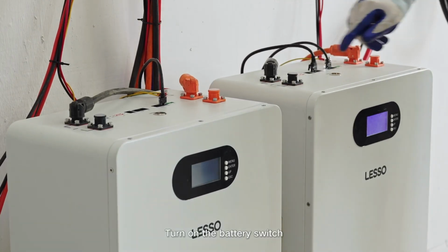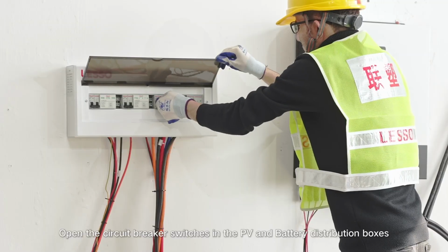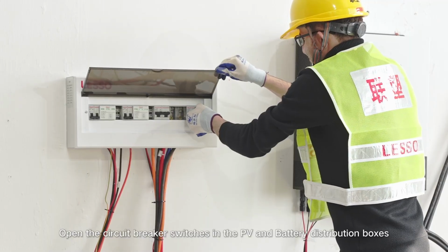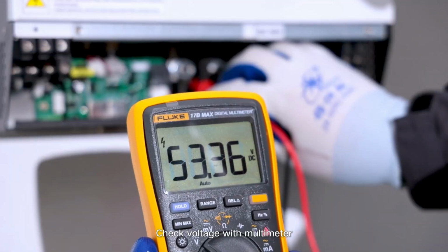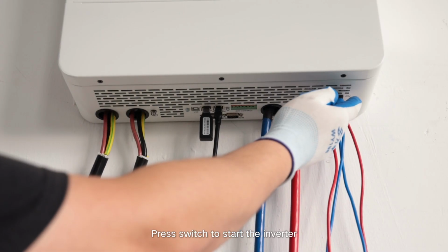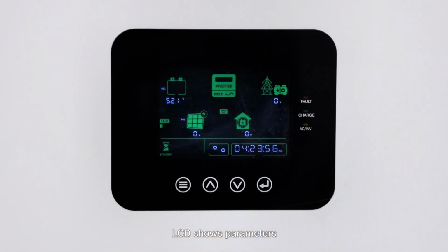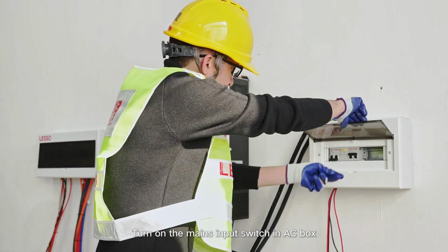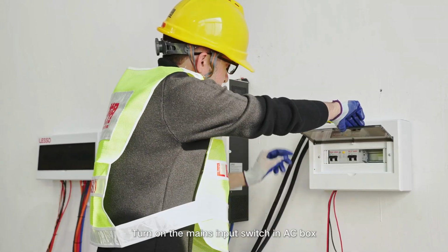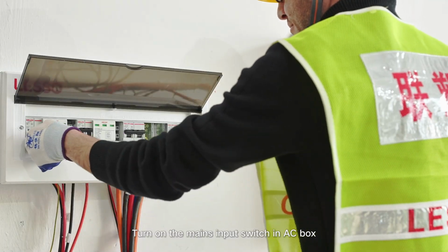Turn on the battery switch. Open the circuit breaker switches in the PV and battery distribution boxes. Check voltage with a multimeter. Press the switch to start the inverter. LCD shows parameters. Turn on the mains input switch in the AC box. Display setting.